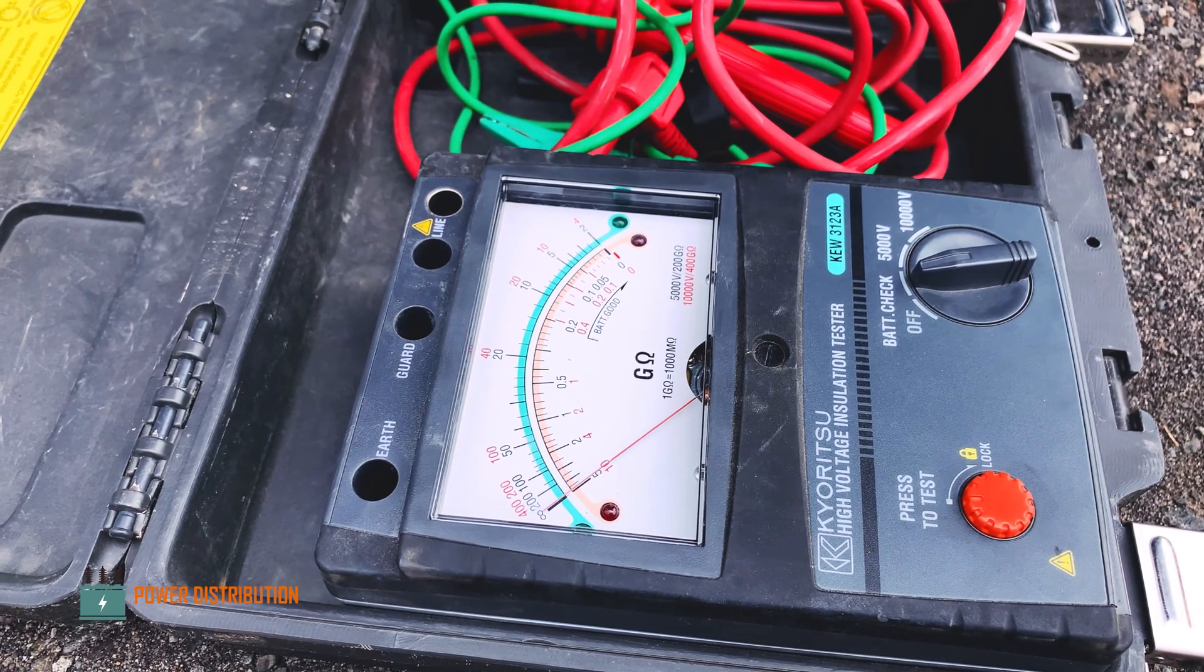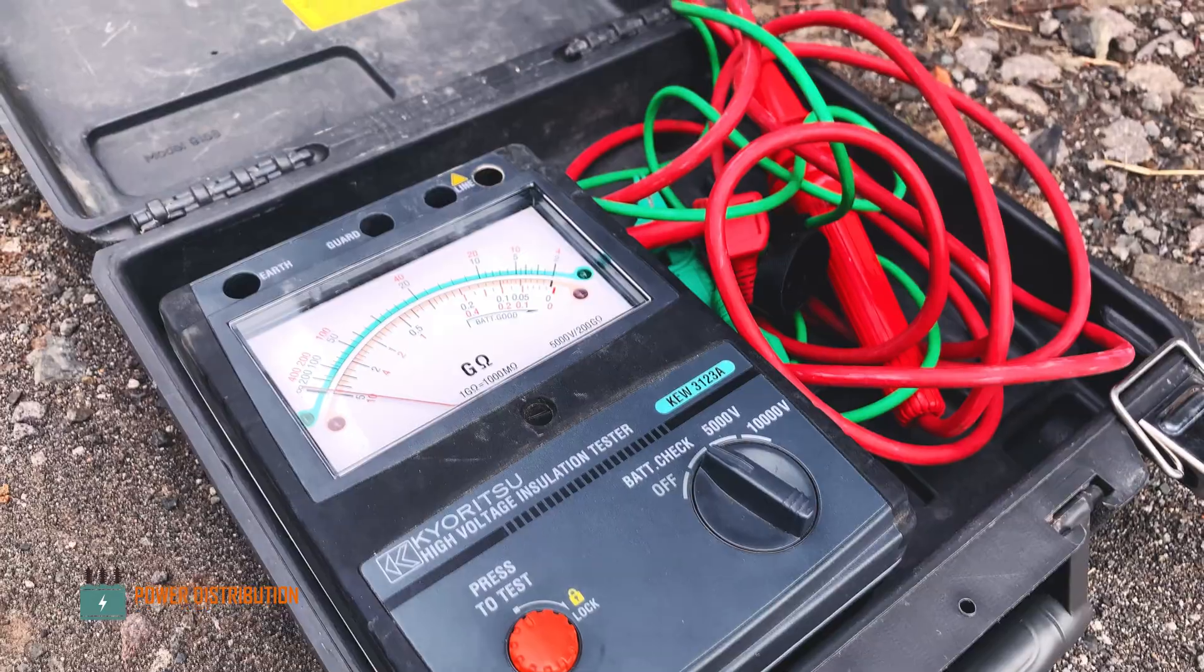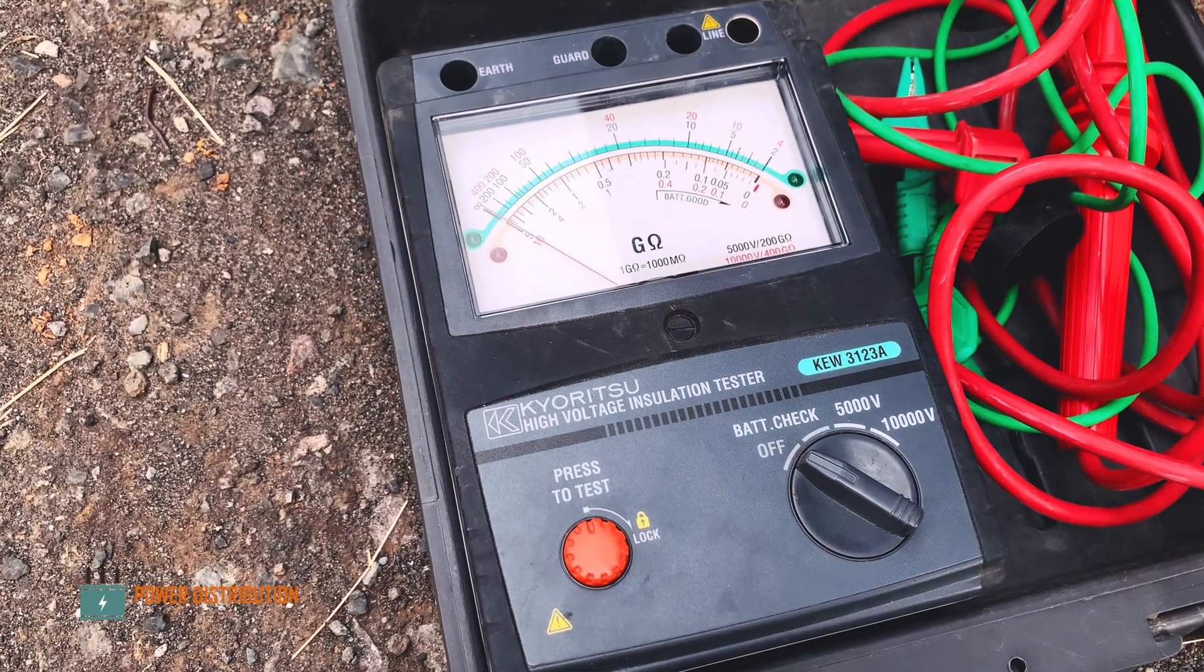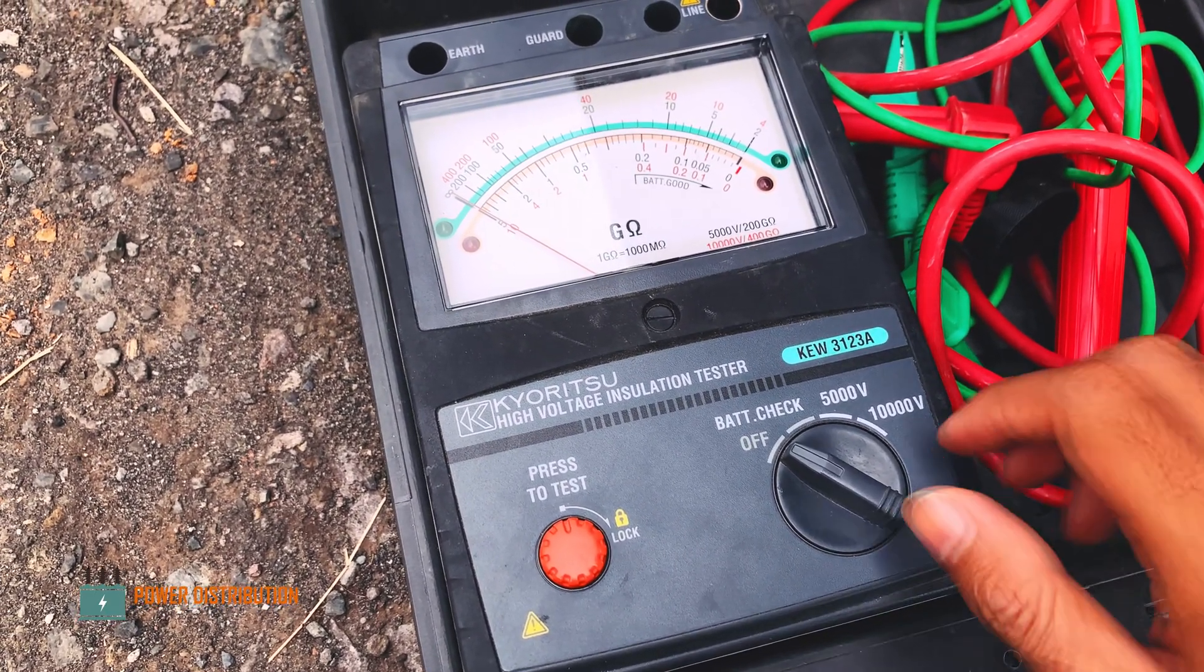The basics are pretty much the same, but in this case it's much easier using the same equipment, which is a high voltage insulation tester from Kyoritsu. Before we use this device to measure, make sure that we have enough juice on the battery.